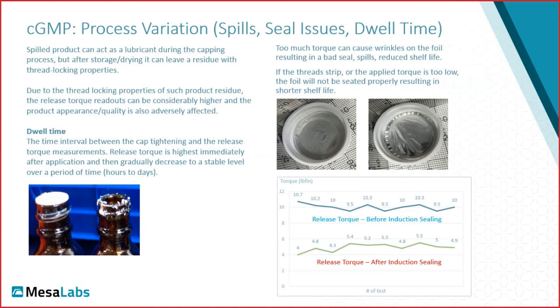So be aware of that. I've been to customer sites where that was an issue, but more commonly problems are related to not understanding that it's important to control the dwell time. That's the time between the application and the removal measurement. So always tell operators to test the removal torque in a specified time after the application. Whether it's 5 minutes or 10 minutes, it doesn't really matter.